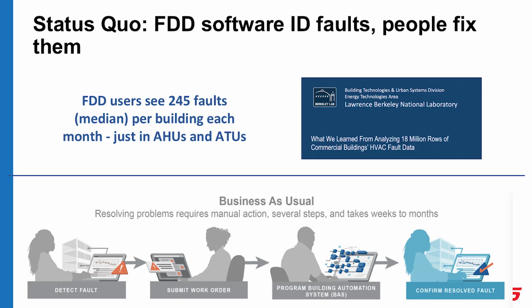And that's only for just AHUs and terminal units, right? So there's this flood of data that all of a sudden these folks are being exposed to, and it's just like overload, right? It's like, number one, all that stuff gets silenced. Number two, there couldn't possibly be enough staff around to even address these faults in the first place. So the FDD tool shows you the fault exists, but then there's this whole process that someone has to undergo to actually get that fault resolved. And this can take weeks, if not months, and that's being generous, right?